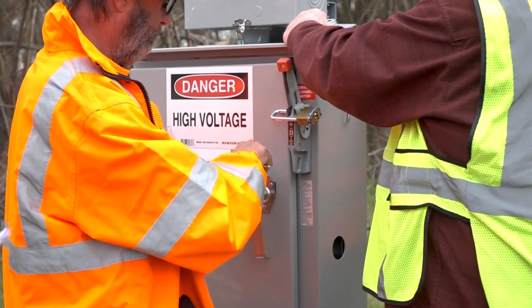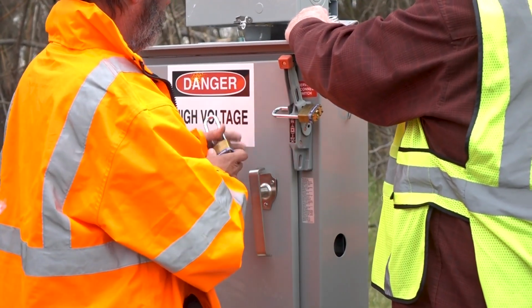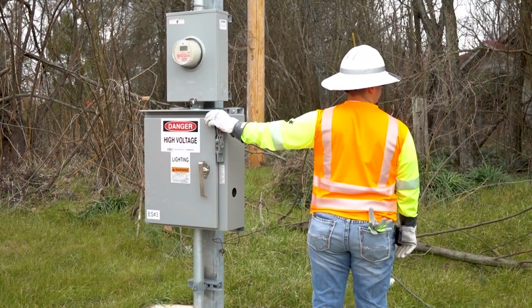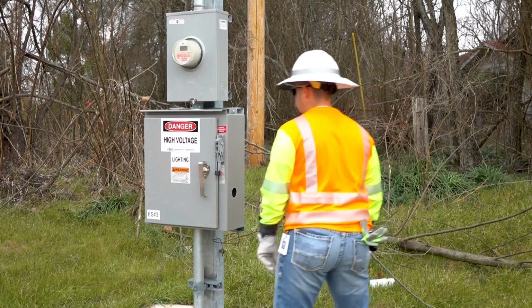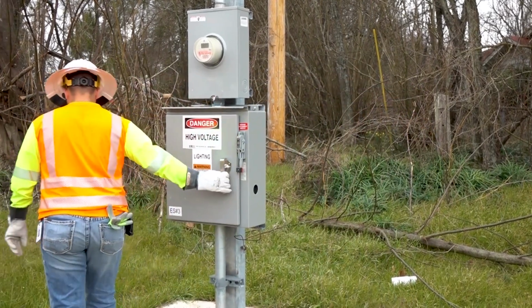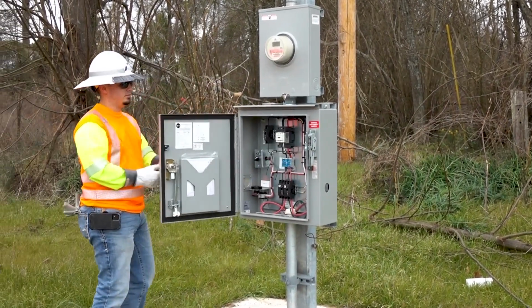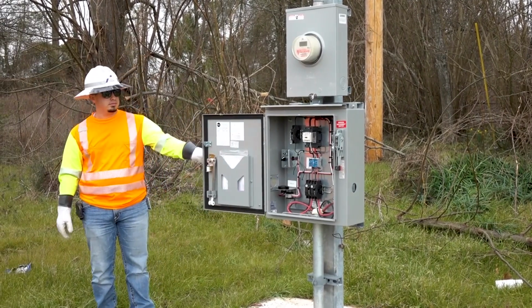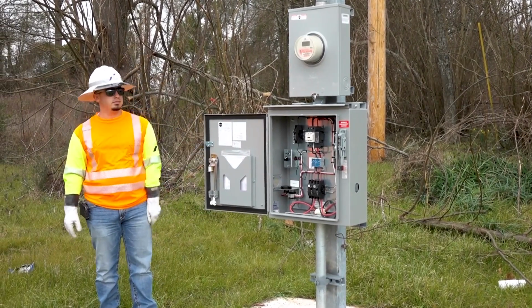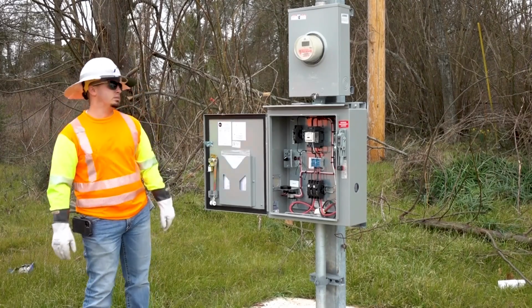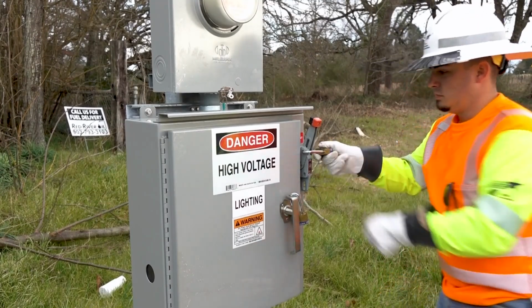A Type A service enclosure must be provided with a stainless steel lockable handle controlling the door latch. For enclosure doors less than 36 inches in height, the door must latch at one or more points. For enclosures 36 inches in height or larger, the door must latch at 2 or more points. The door handle will be locked with a master number 2195 padlock.